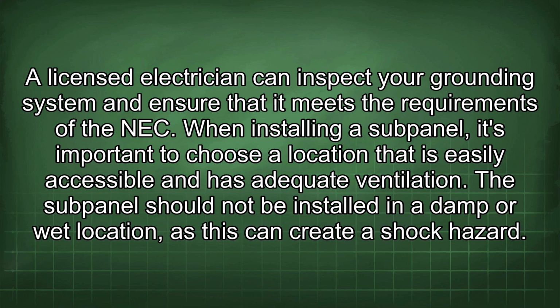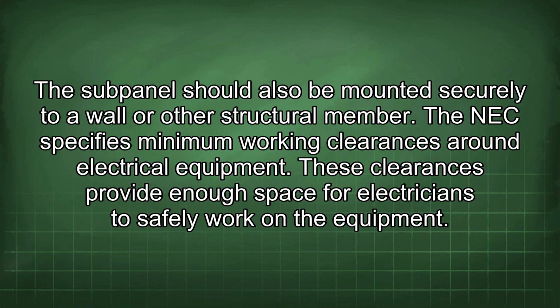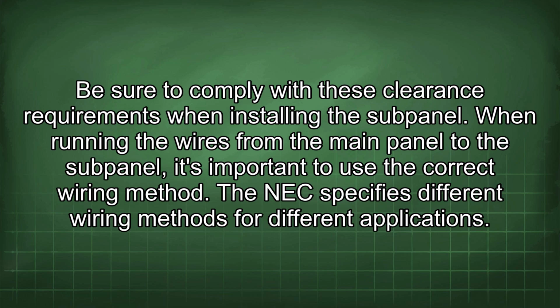When installing a subpanel, it's important to choose a location that is easily accessible and has adequate ventilation. The subpanel should not be installed in a damp or wet location, as this can create a shock hazard. The subpanel should also be mounted securely to a wall or other structural member. The NEC specifies minimum working clearances around electrical equipment. These clearances provide enough space for electricians to safely work on the equipment. Be sure to comply with these clearance requirements when installing the subpanel.